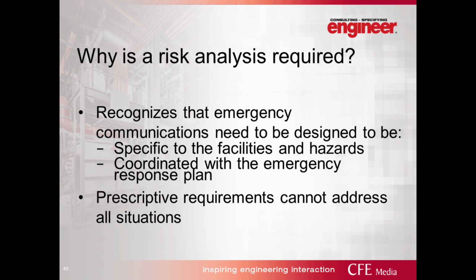Like I said earlier, it could be weather-related, Tornado Alley, or hurricane areas. Or we could have industrial hazards that might justify having a mass notification system. Chemical plants, for instance, oftentimes will have wide area signaling to neighboring communities. If they have an accidental release, they'll automatically notify occupants that would be in the plume, or in the direction of the plume as it travels, to warn occupants. So that's actually a mass notification system. So the committee realized that prescriptive requirements really couldn't address all the situations.